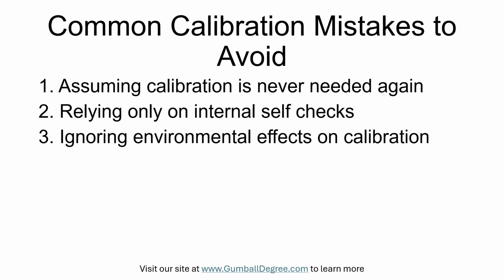Another error is relying only on internal self-checks without using certified standards or external verification, and the fix is to include independent reference checks whenever possible. A third mistake is ignoring environmental factors like temperature and humidity that affect calibration, so monitor and control the lab environment or add extra calibration checks after significant changes.